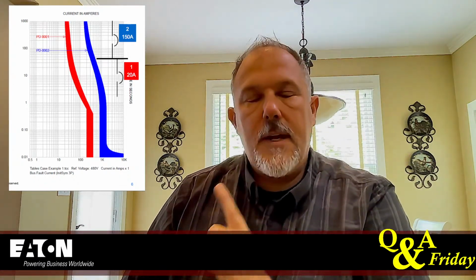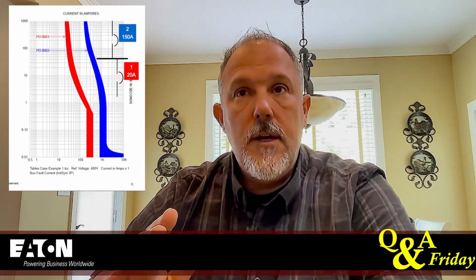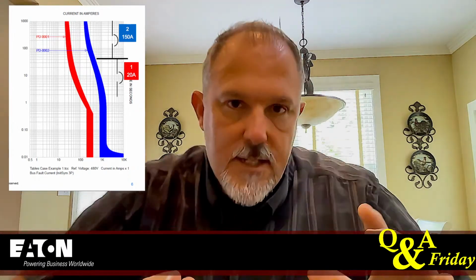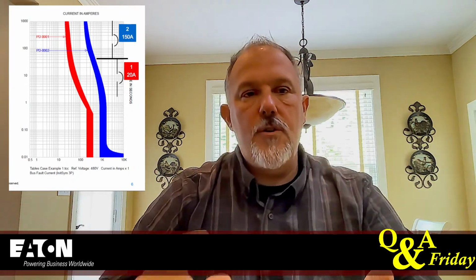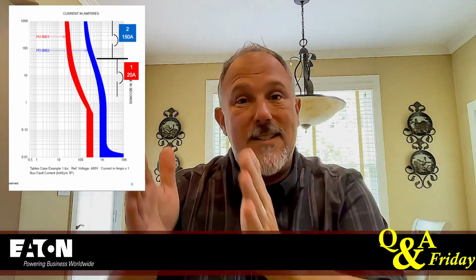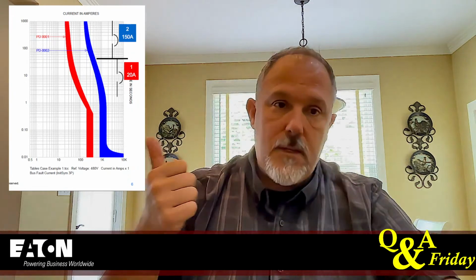So the question that came in from one of my viewers was, and I get this question a lot, and that's why I honed in on it: what happens if my fault current is greater than 1500 amps, Tom? How do I address the problem? Now, what I told you was the goal of that session that I did, and check my YouTube channel, you'll find it. It's one of my most viewed videos on how to interpret the selective coordination tables. I had one for breakers and I have one for fuses. I'm just helping you understand how to use the tables. But let's say that the tables tell you 1500 amps and you've got 5000 amps of available fault current. What do you do to address selective coordination?